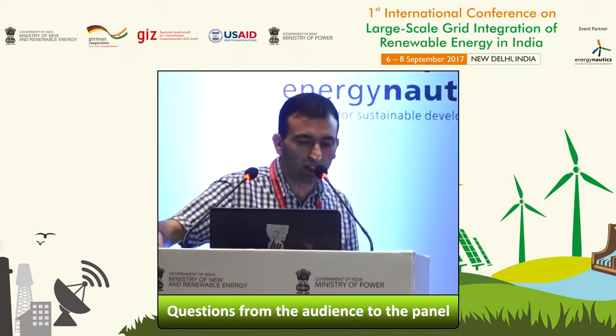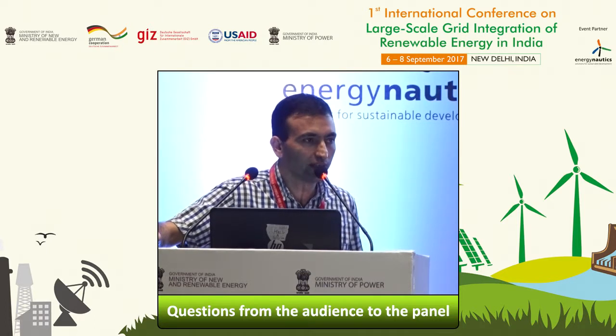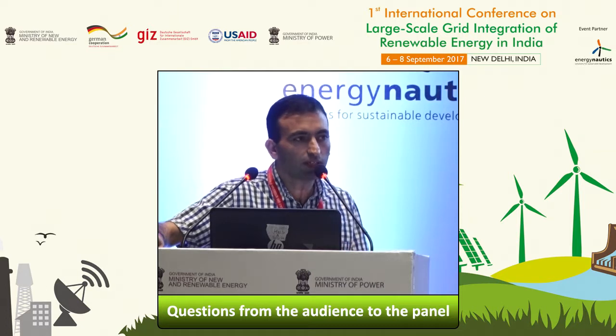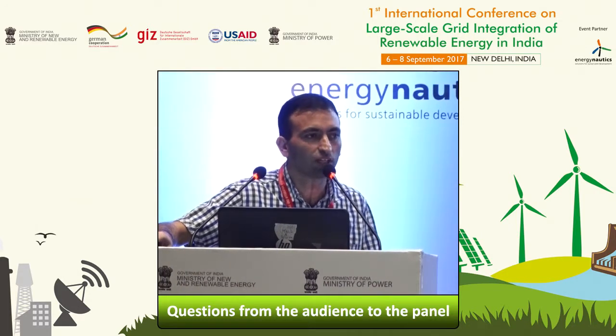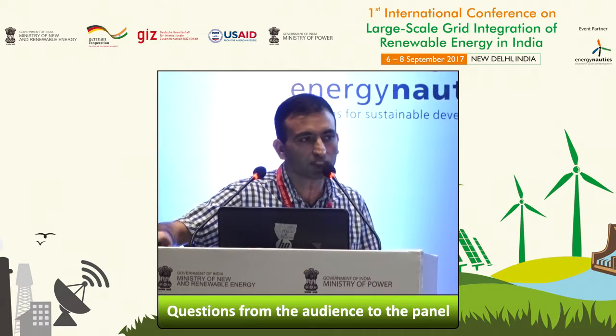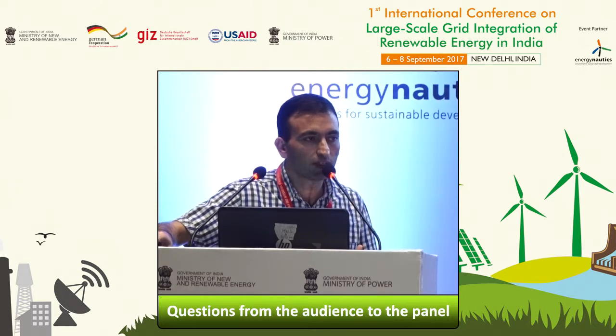The recommendation is, I am not commenting here in the context of the Indian LVRT requirement, because the Indian LVRT requirement requires active power priority. So I am trying to understand why active power priority. There might be some reasons behind it, but generally in large systems it is reactive power priority. But in some cases, for whatever reason, when we go for active power based LVRT, the intention is that we have more active power injection into the grid during this LVRT requirement.